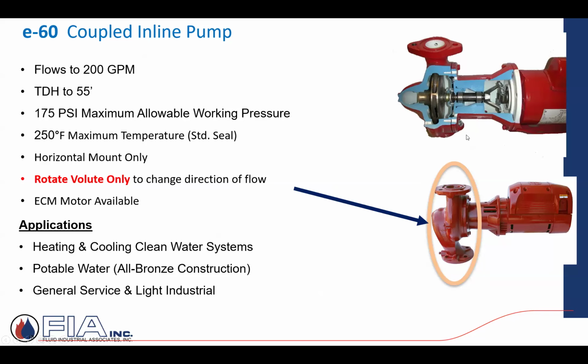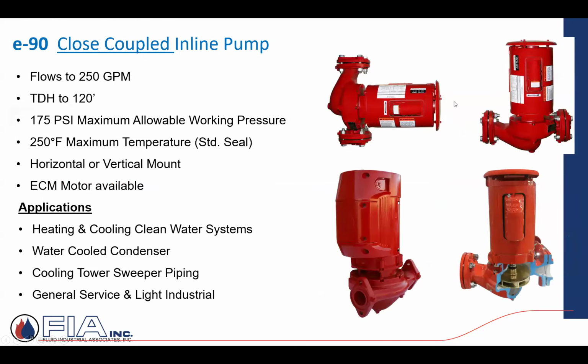In Bell and Gossett's world, it's the Series E60s, but it's a horizontal inline pump with a coupler, I should say. And that coupler is connecting the shaft from the motor to the shaft of the impeller with this coupling. Next family, if you will, same inline pump. It's just called an E90, and it can be mounted in both orientations, vertical and horizontal.